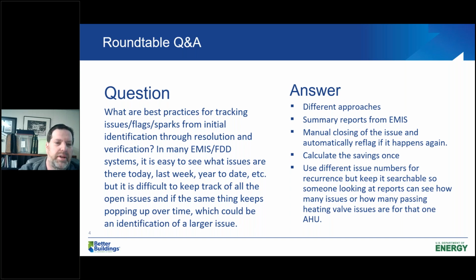Can this identify bigger issues? What if we find a few things - does it create an opportunity to find bigger issues? I recall one site where VAV boxes had problems of either too much air or too little air. They were being identified with damper related issues, temperature related issues, but it was actually a much larger problem. When the O&M team went out there, they discovered it was a flaw in the design of the terminal boxes - plastic wheels on metal that were breaking and affecting the position. So it was actually a much larger problem, but through investigation the O&M team figured out what it was and worked with the supplier on a solution for all their VAV boxes.